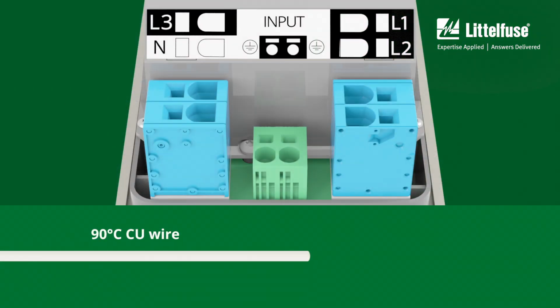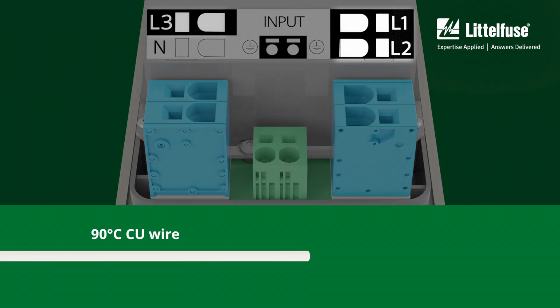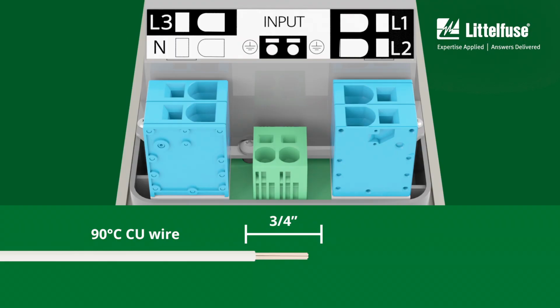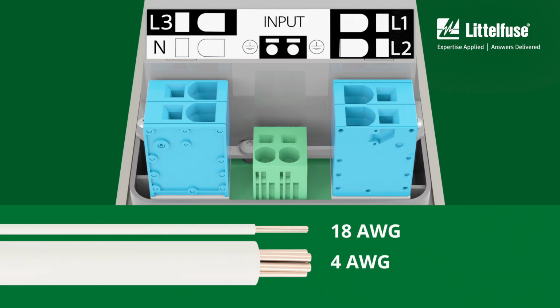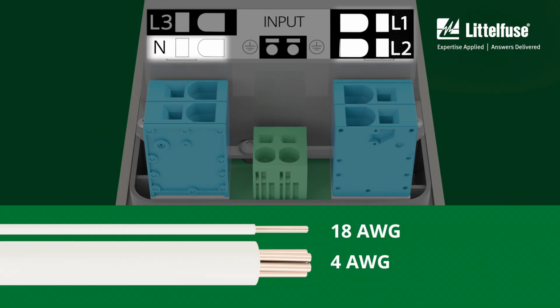Use 90 degrees Celsius rated copper wire. Inputs are L1, L2, L3, and neutral. Strip wires to 3/4 of an inch. Terminals accept 4 to 18 AWG conductors. 2-pole applications use L1 and L2 only, and neutral for split-phase applications.